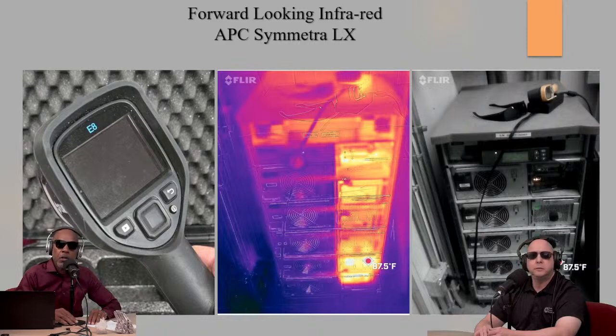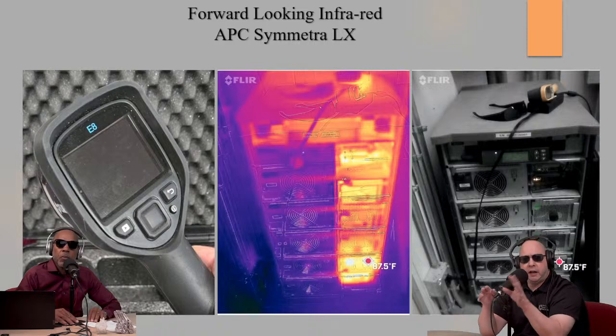Justin asks: do the ground or the output terminal block, talking about where the clips go? With those alligator clips, one goes to the ground wire, 3 go to the power, and one goes to neutral, and that's verifying your voltage, coming out of the unit.